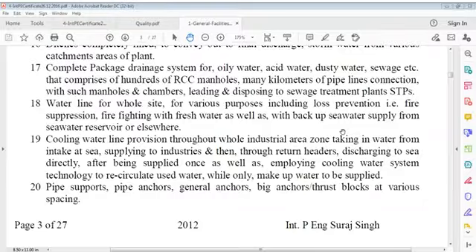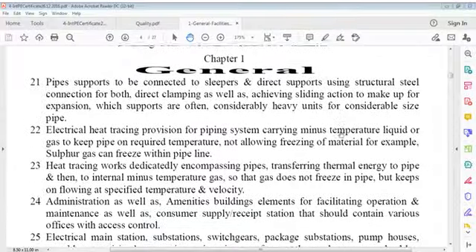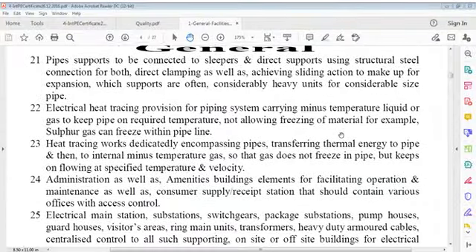Pipe supports, pipe anchors, general anchors, big anchors, thrust blocks at various spacing. Pipe supports to be connected to sleepers and direct supports using structural steel connections for both direct clamping as well as achieving sliding action to make up for expansion, which supports are often considerably heavy units for considerable size pipe. Electrical heat tracing provisions for piping systems carrying minus temperature liquid or gas to keep pipe at the required temperature, not allowing freezing of material. For example, sulfur gas can freeze within pipeline.